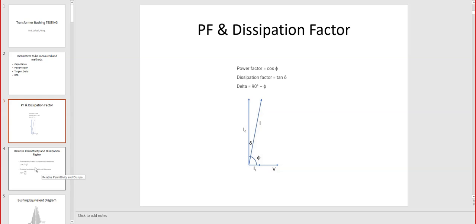And then you will see that dielectric frequency response is reading these values at different frequencies. So basically it is not a totally different test, because this test that we call power factor and dissipation factor happens at 60 Hertz. But if we want to do this test at other frequencies, then that becomes dielectric frequency response, which is narrow or wide. We will see that in a following slide. So is this reading also affected by the temperature? The temperature we want is 20 degrees Celsius.